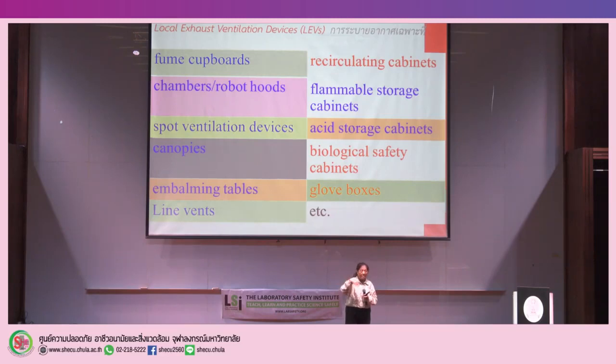There is no air coming in, no supply air flow. And you try to use a device that exhausts air out. So it's going to work so hard. The motor is going to work so hard, but very little will go out, or it makes your room like a vacuum. That's why most of the time the lab door cannot close, it opens by itself, or it's difficult to open if you want to push it open.